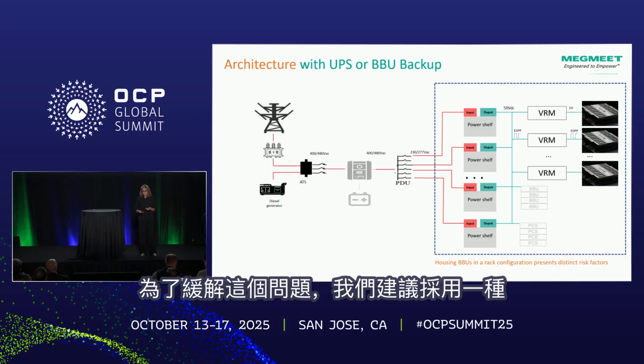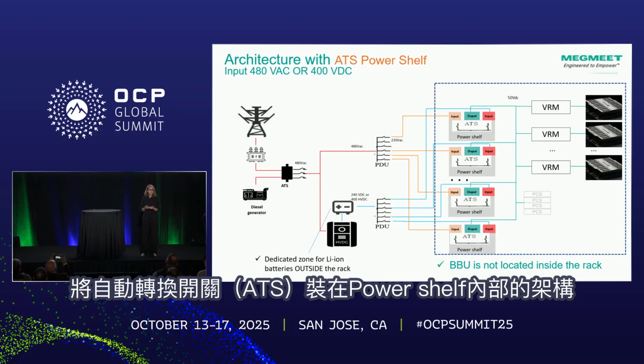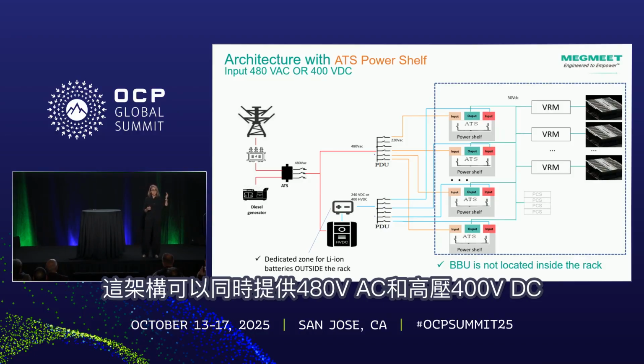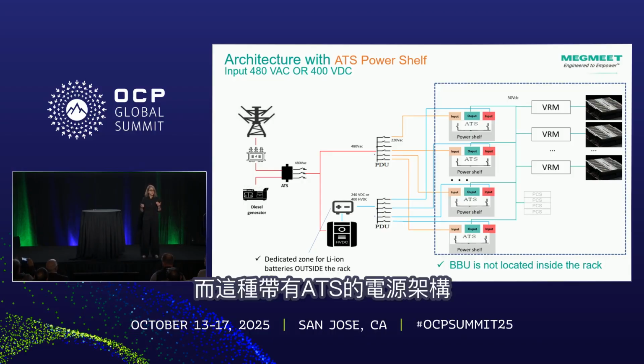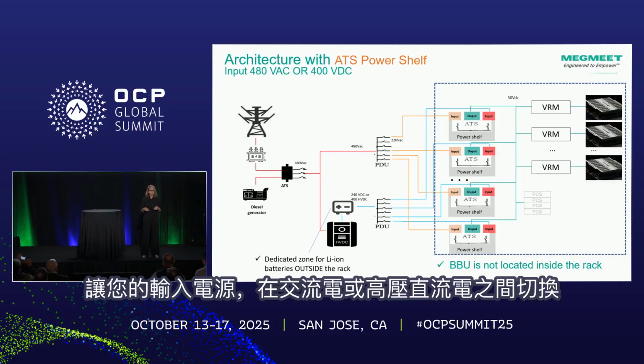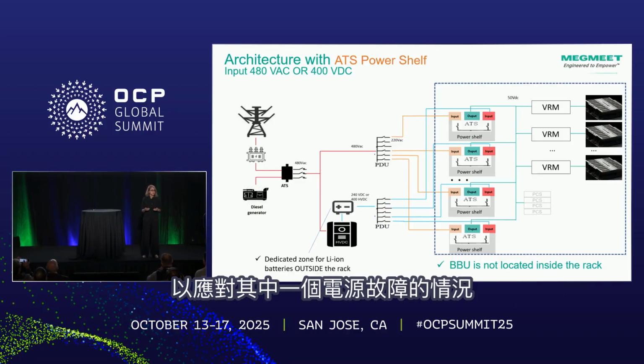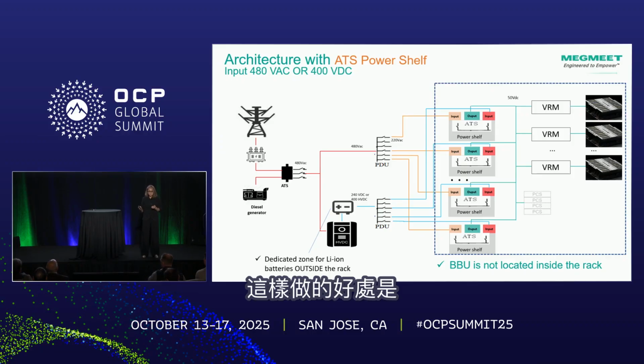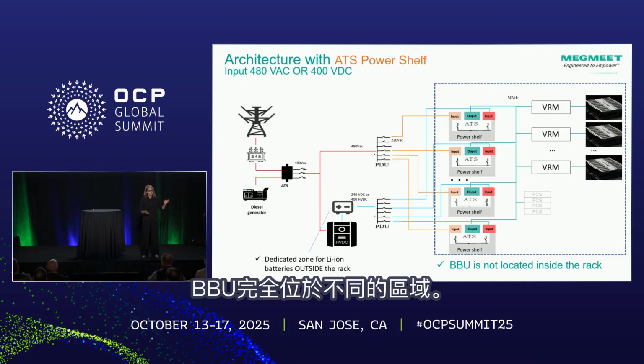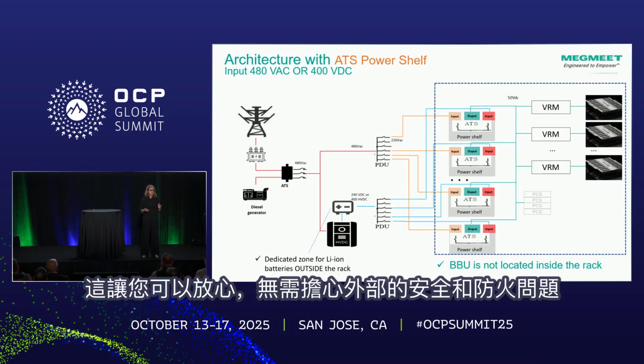So to mitigate that, we recommend an architecture that is having the ATS power shelf inside the power supply. So there are structures that you can get the high voltage AC, 480 volts, as well as the high voltage DC, both of them in the structure, and have this power shelf with ATS allows you to have alternate sources between AC or HVDC in terms of if there is one failure. And that benefit is that the BBU is completely in a different zone, giving you that benefit to have that concerns about safety and fire outside.